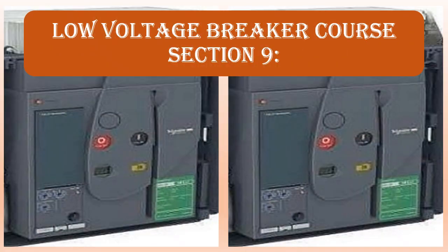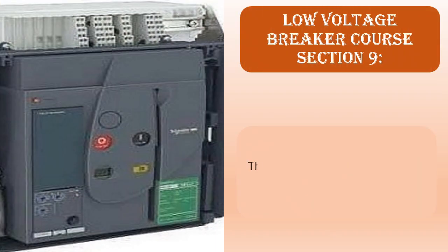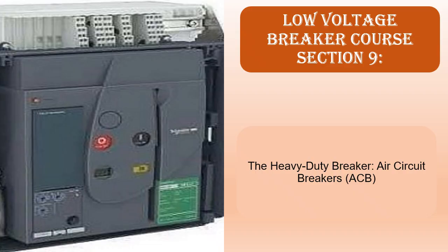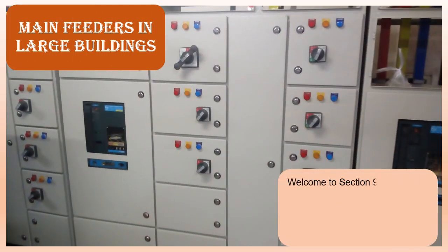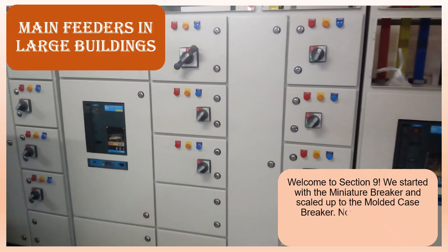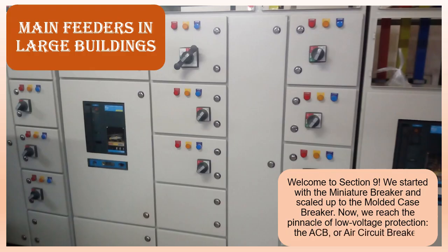Low Voltage Breaker Course Section 9. The Heavy Duty Breaker, Air Circuit Breakers, ACB. Main feeders in large buildings. Welcome to Section 9. We started with the miniature breaker and scaled up to the molded case breaker. Now, we reach the pinnacle of low voltage protection, the ACB, or air circuit breaker.